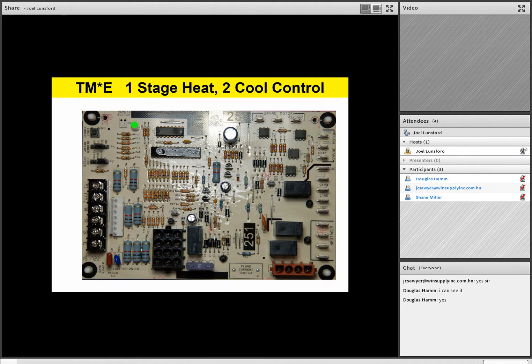So let's go ahead and start out with Y1. Y1 is your first stage cooling call. In this example, as we talked about in our previous little block diagram, if the indoor unit has Y1 and Y2 terminals, this would be a great example of that type of board. So Y1 is your first stage cooling call. Y2 is your second stage cooling call. Now again, these are your thermostat connections going up to your thermostat.